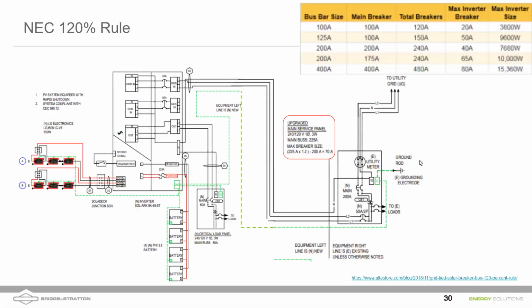We upgraded the panel. We took the panel out. It was an old Zinsco, old GE panel anyway, so it needed to be upgraded. We put in a 225 amp bus. The 120% rule allows us to backfeed the panel up to 120% of the bus bar rating. So in this example, 225 times 1.2, we could actually have gone up to 70 amps.